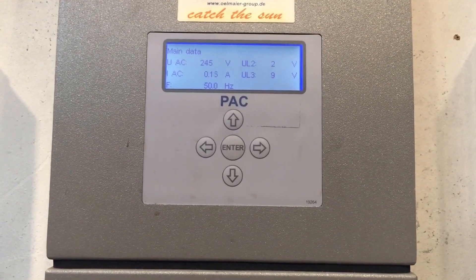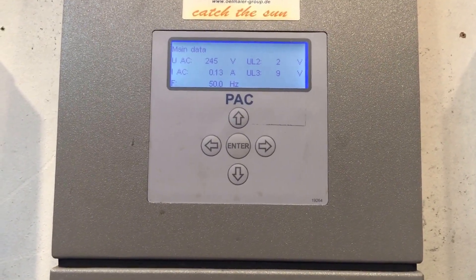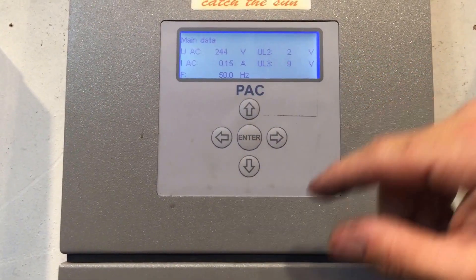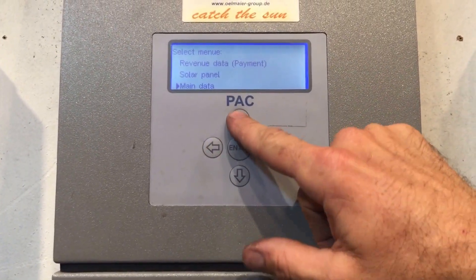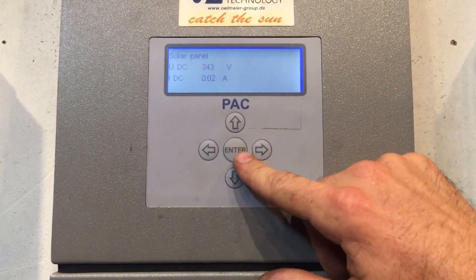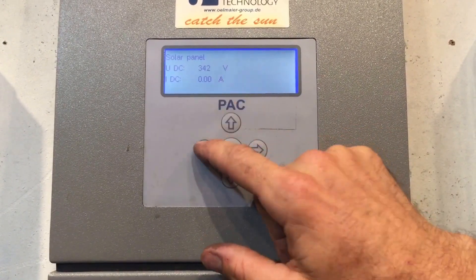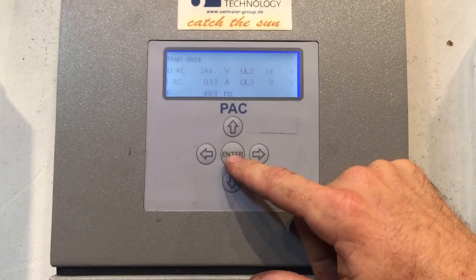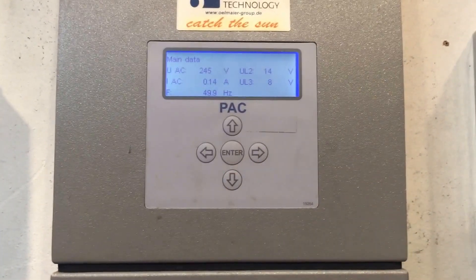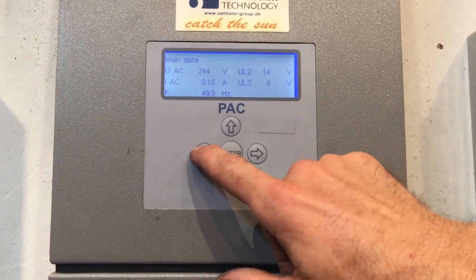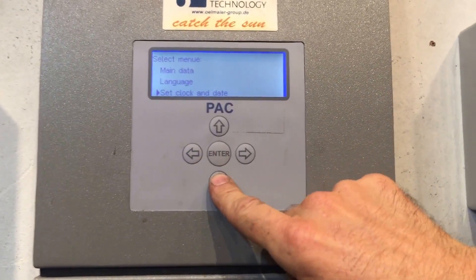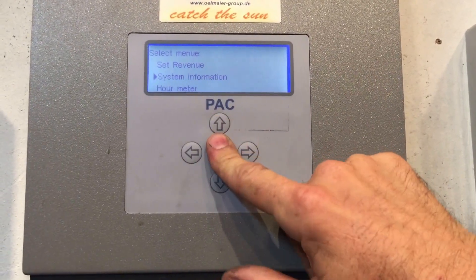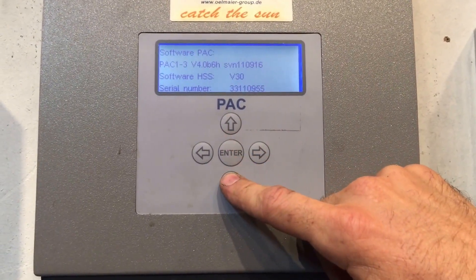So we've confirmed the inverter has power from the street — it's got the AC voltage — and the solar panel voltage is there too, but still zero amps. This system is not working at the moment. Going back to main data shows that voltage and frequency again, and then there are other menu options: language, set clock, date set, revenue, and system information.